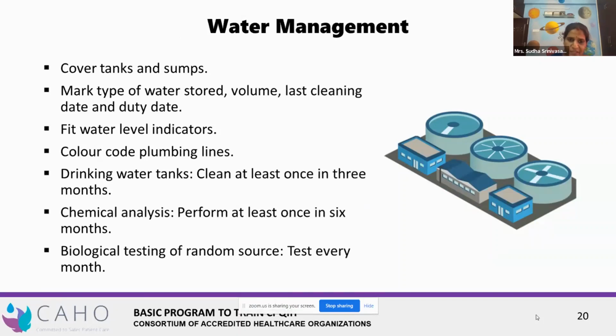Identification of the average consumption in your hospital needs to be calculated. You also need to identify the different tanks and sumps available, meaning overhead tanks. You may have different tanks for storing different types of water - one for drinking water, one for RO water, one for fire pipelines. So it could be different, and each has to be clearly labeled with the type of water it actually contains.